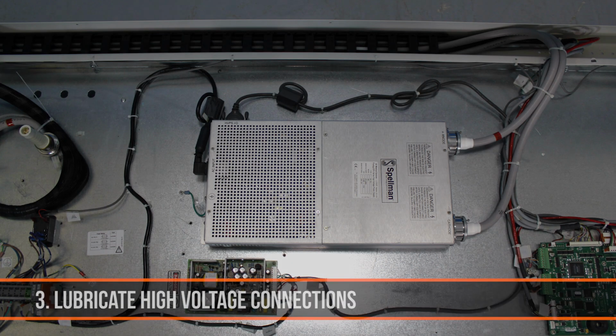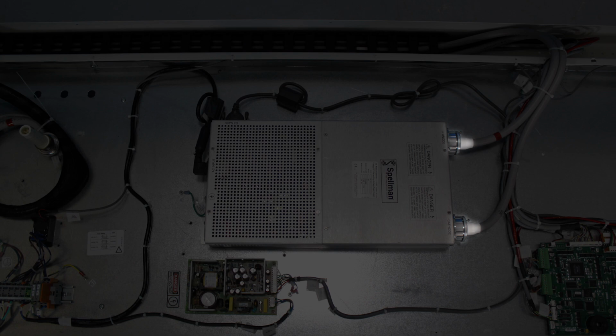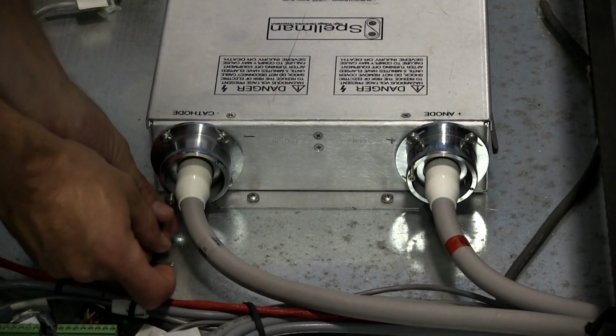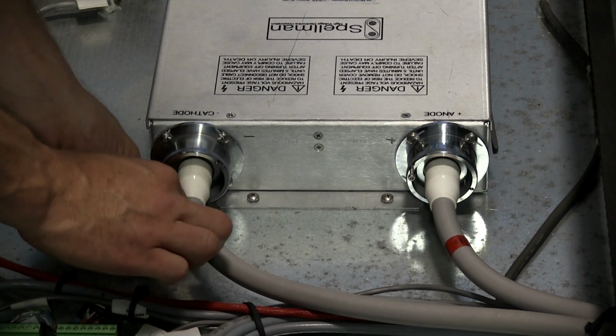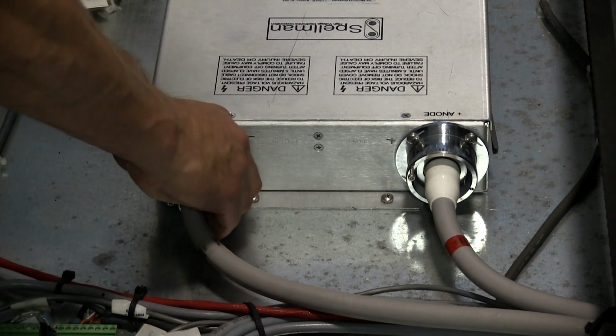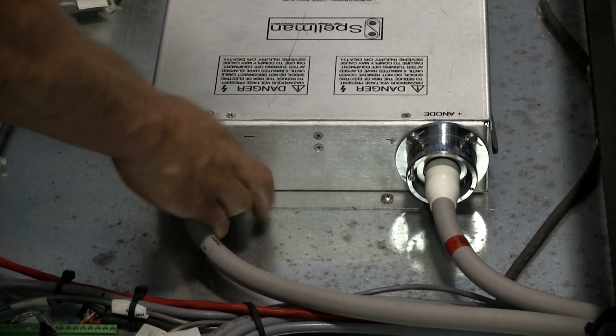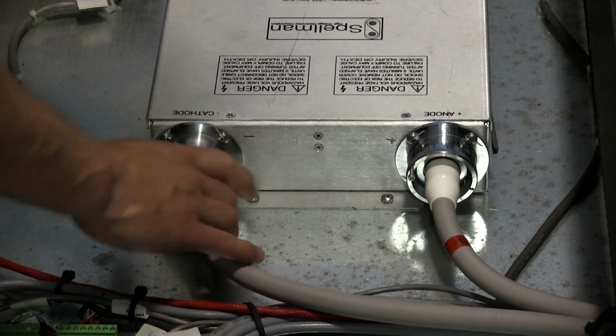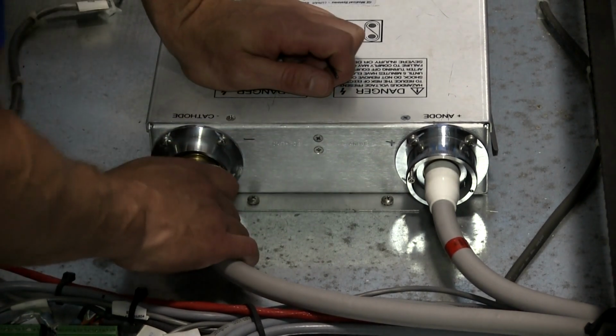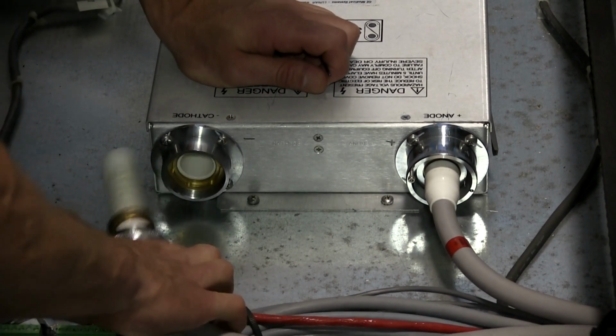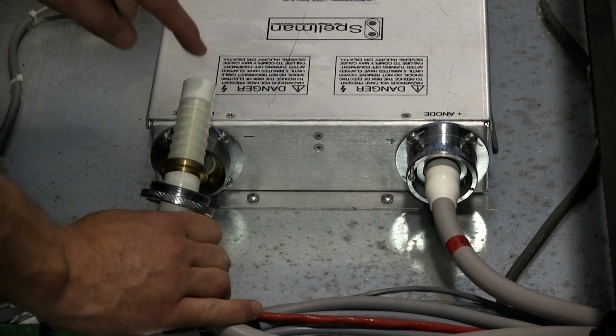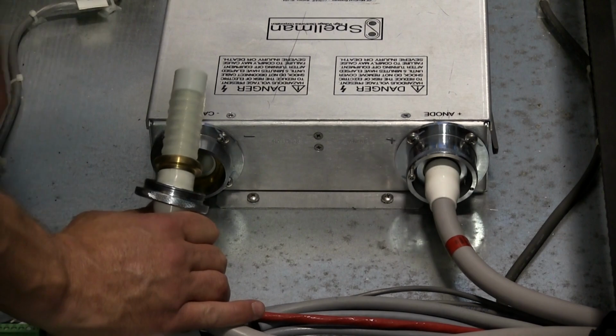We need to ensure that we have proper lubrication on the high voltage connections. To do so, loosen up the set screw on your high voltage connection, unscrewing it and pulling it straight out. Once the connection is out, you're going to lubricate a little bit of oil down the edge and just a few small drops on the internals where the four prongs are.